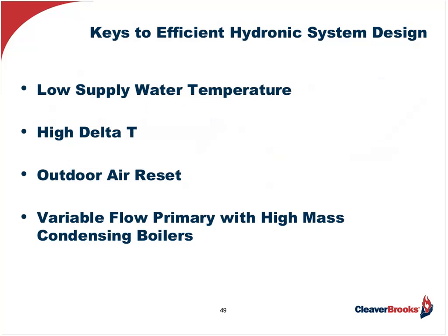So to design a high efficient hydronic system, use as low a supply water temperature as possible. 160 is good, 140 is better. Use the highest delta T as possible. Again, ideally 40 degrees or higher. If you can't do those, use an aggressive outdoor air reset to get that cold water back to the boiler. And then finally, wherever possible, use variable flow primary pumping with high mass condensing boilers.